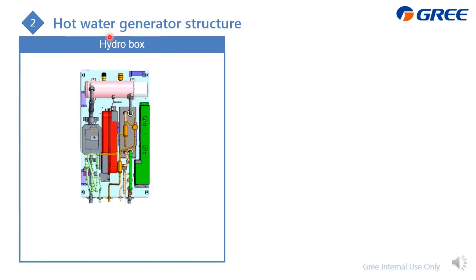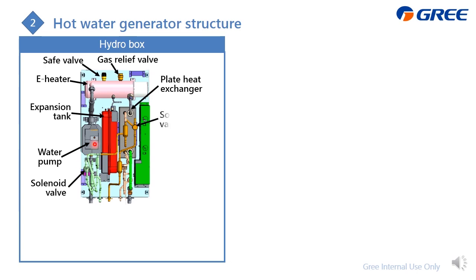As for the inside structure of the hot water generator, first we will have a look at this hydro box. Just open the panels. Here is the inside, and you can find that we have the solenoid valve, water pump, expansion tank, and this one is the e-heater. Here is the safety valve and gas release valve, and this is the plate heat exchanger to exchange heat between the refrigerant and the water. And also here is the solenoid valve. This is the EXV, and here is the water filter, and this green one is the electric box.